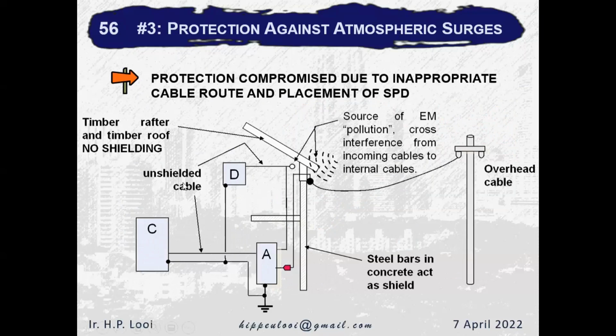I got a call that their equipment keeps burning. They said it cannot be, because the design engineer was very smart and put in a surge arrestor. But how come this equipment is still burning? What happened was that this roof was a timber roof, so there was no shielding, and because this cable was exposed, it caused the damage. So what happened is you put a surge arrestor here.